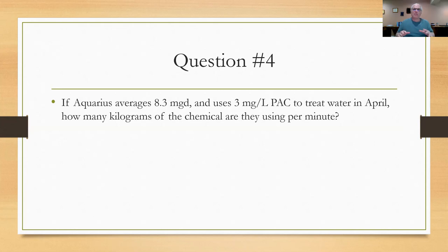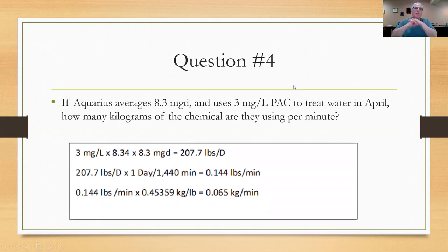The way I set this up was this way. With the standard formula up there for 3 milligrams per liter at 8.34 pounds per million gallon for every 1 milligram per liter times the flow rate of 8.3 MGD, I come up with a usage of 207.7 pounds per day. If I take that 207.7 pounds per day and divide it by 1440 minutes, I would get 0.144 pounds per minute. I take the 0.144 pounds per minute, multiply by 0.45359 kilograms per pound, I come up with 0.065 kilograms per minute. Hope you got that right. If you did, you've gotten four out of the five correct already. You've got an 80%, you passed. Let's try the last one. It's a little bit more difficult, a little bit more involved. In fact, I needed two slides to do this one.